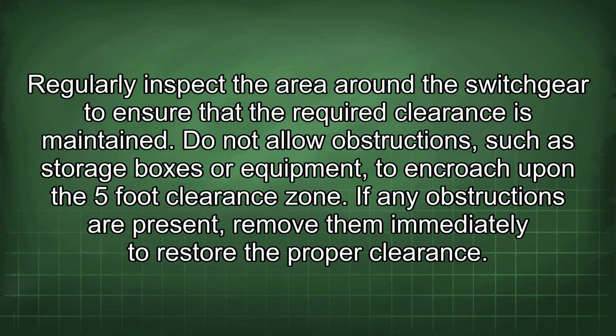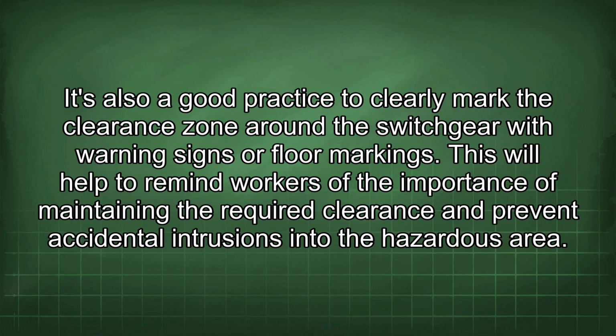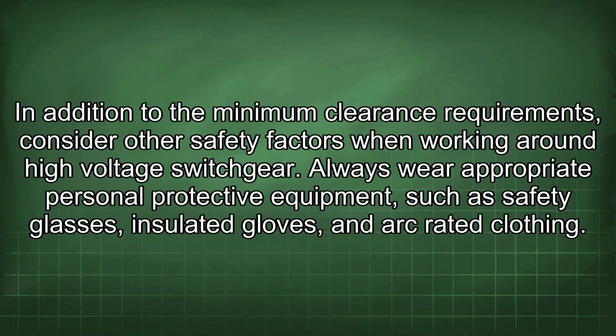Regularly inspect the area around the switchgear to ensure that the required clearance is maintained. Do not allow obstructions such as storage boxes or equipment to encroach upon the 5-foot clearance zone. If any obstructions are present, remove them immediately to restore the proper clearance. It's also a good practice to clearly mark the clearance zone around the switchgear with warning signs or floor markings. This will help to remind workers of the importance of maintaining the required clearance and prevent accidental intrusions into the hazardous area.